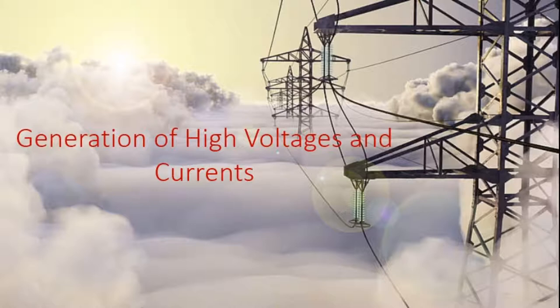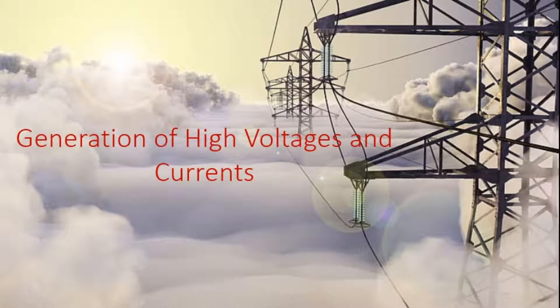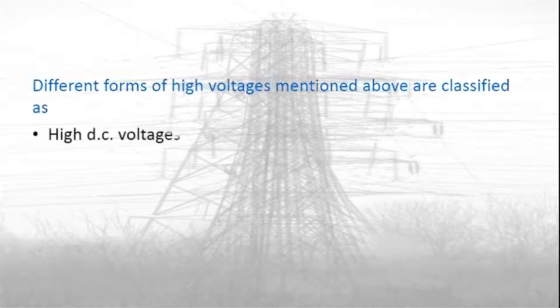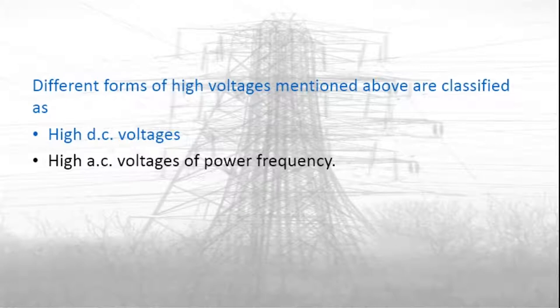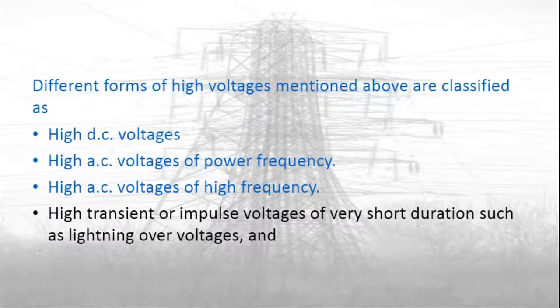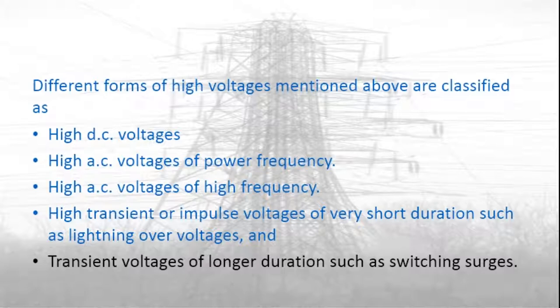High impulse voltages are required for testing to simulate overvoltages that occur in power systems due to lightning and switching surges. These are the major purposes of generating very high voltages in the laboratory for testing. The classifications include high DC voltages, high AC voltages of power frequency, high AC voltages of high frequency, high transient or impulse voltages of very short duration such as lightning voltages, and testing transient overvoltages of long durations such as switching surges.